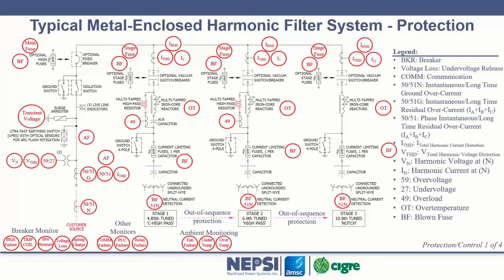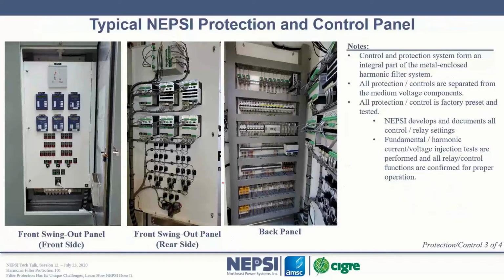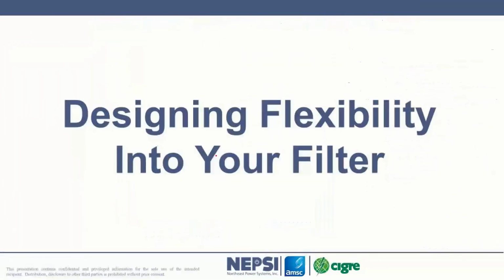This is just a snapshot of a typical 3-stage system and all the protection and control that we would typically provide. Actually, this is a protection diagram only. These are ANSI device numbers, but we define what they mean over here to the right. So again, go back to the video if you're interested in this. Another thing to note is we want to make sure we have no out of sequence control of the bank. Generally speaking, multi-tune filter banks must step up and step down in sequence. So that's part of the control scheme. So, just kind of another picture.